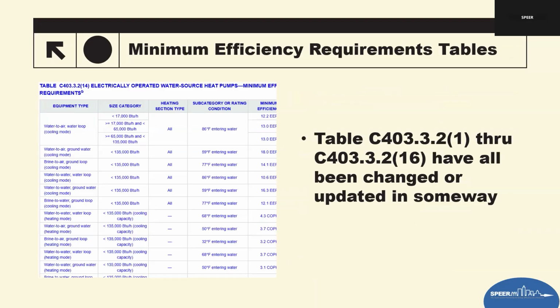So in the 2024 IECC mechanical systems section, nearly all the minimum efficiency tables have been updated, reorganized, or adjusted. I didn't put all of them on here, but tables C403.3.2(1) through C403.3.2(16), have all been changed in some way. Everything shows up in blue text if you go to iccsafe.org. All those cover air conditioners, heat pumps, water source units, VRFs, and hydronic equipment, and all have been revised. Some tables receive new efficiency values, others have just been reorganized, and some have been updated to align with federal minimums or AHRI rating conditions.